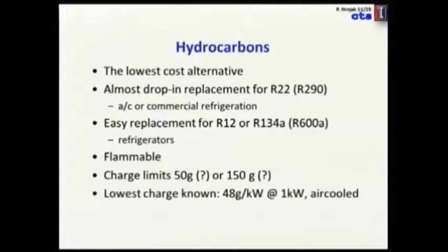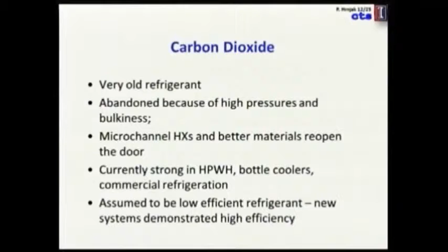Now carbon dioxide is a very old refrigerant, same as ammonia, and it was originally abandoned because of high pressures and bulkiness. Microchannel heat exchangers and other technology advancements have brought it back, and yet it's assumed to be a low efficiency refrigerant, so I'll spend a few slides explaining what I think about that particular issue.